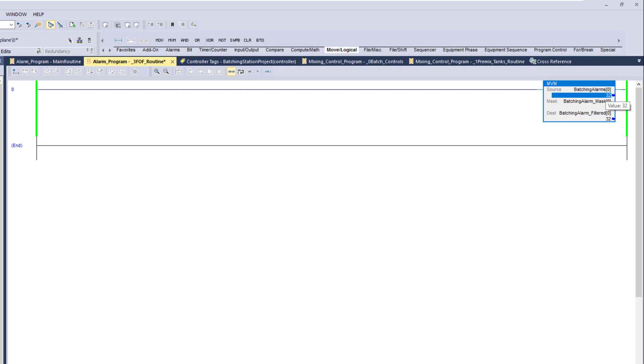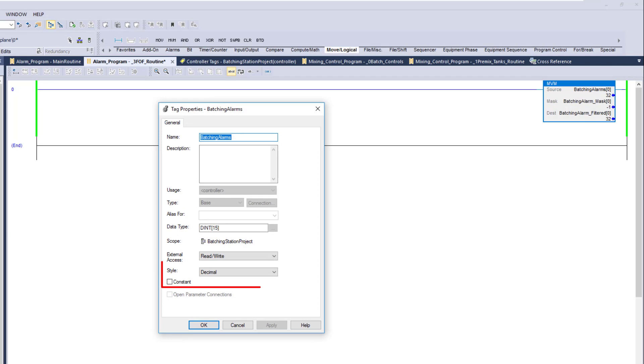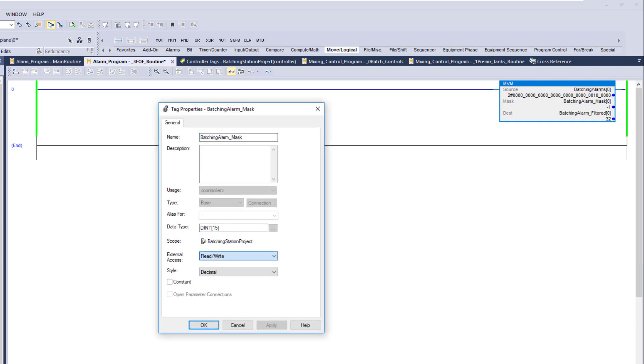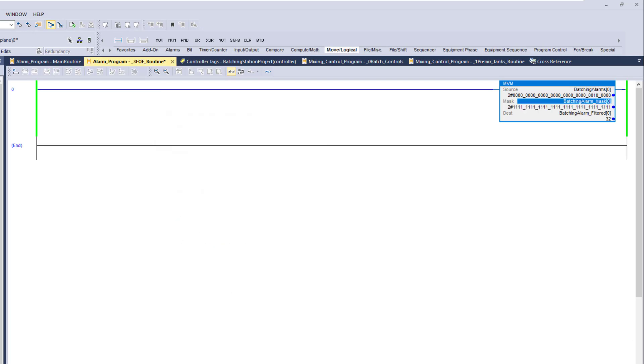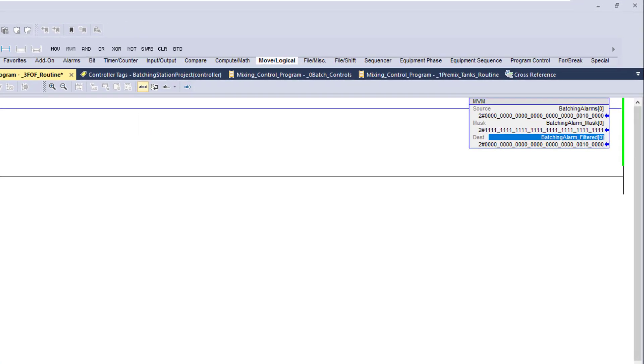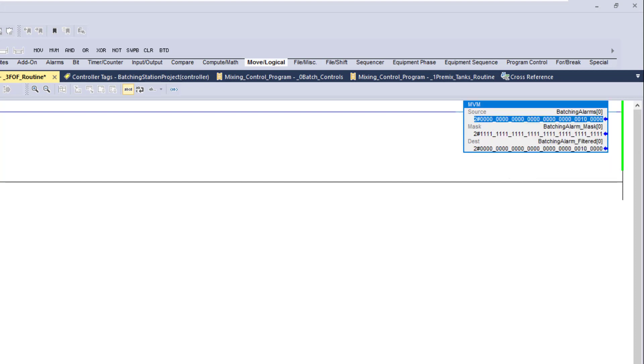We're currently in decimal form. If we change the display style to binary, you can see the binary representation of that decimal value. Go to Edit, change to binary, and you can see the exact mask being used. This shows how we pass the binary form of the source through the binary enable/disable pattern of the mask to arrive at the destination — right now every single bit is enabled, so everything passes through.